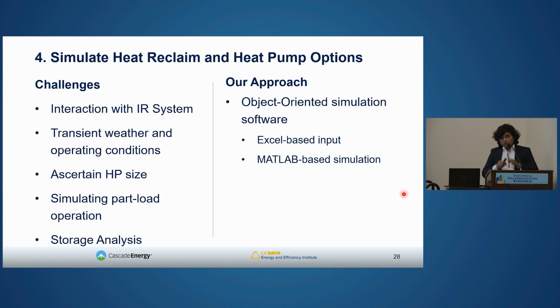Moving on, after developing the pinch analysis and the system integration designs, the next step was to simulate these options and see how they performed throughout the year. We wanted to see this in detail because we were tying our heat pump system to the refrigeration system, so we looked at the interaction with the industrial refrigeration system, how we performed under transient weather and operating conditions, what heat pump size performs best whether oversized or undersized, the part load efficiencies for both the heat pump and refrigeration system, and the optimum size for storage in our heat reclaim and heat exchange loop.